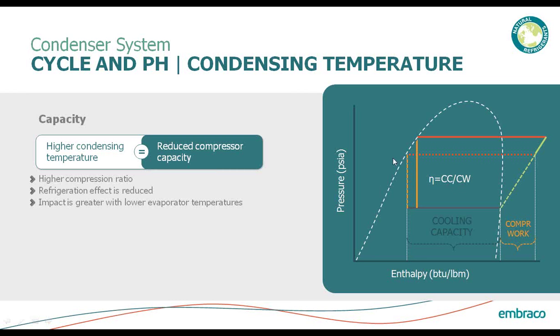It's a cost trade-off that you need to balance — what costs more, more compressor or more condenser? And consider what type of condenser you use: whether you use a micro-channel, which gives you more heat of rejection in a smaller volume, or shrink the tubes of your condenser. There are good reasons for a small condenser too, such as limited space. Just be aware that you're impacting your cooling capacity. This effect is magnified greatly as the evaporator temperature of your system decreases, so low temperature systems have a much greater impact on this than a medium temperature system.